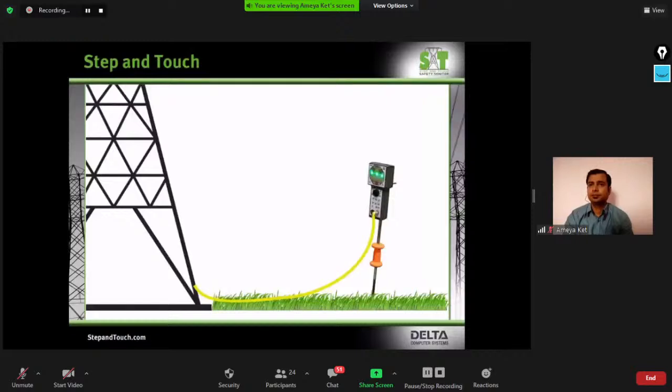When the SNT senses dangerous voltage levels, it will alarm. Yellow LEDs will flash if the potential reaches 100 volts. If it reaches 500 volts, red LEDs will flash. You can silence the audible alarm while you remedy the ground potential rise situation. The visible alarm will continue until the voltage falls to a safe level and you clear the alarm.